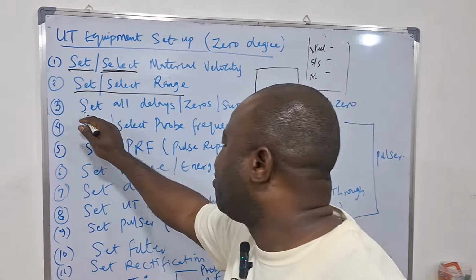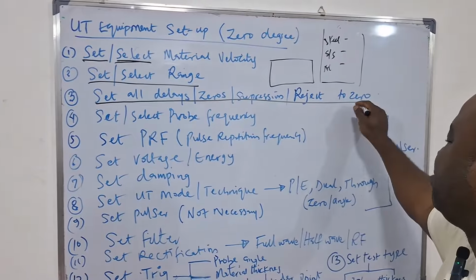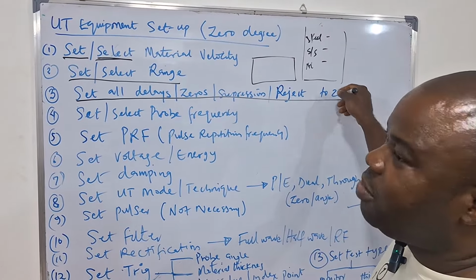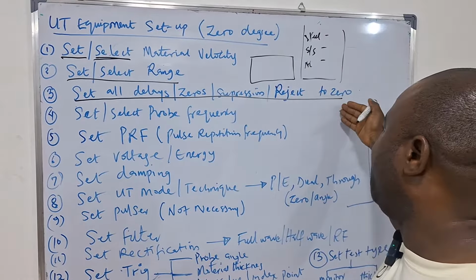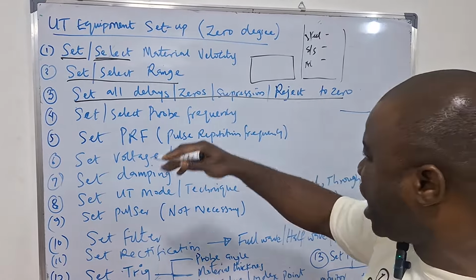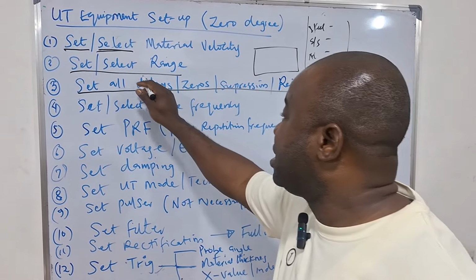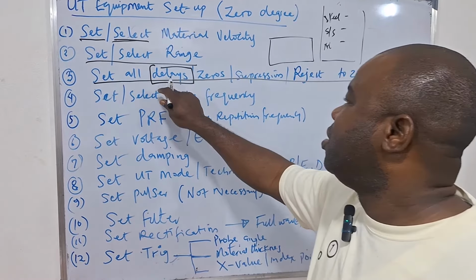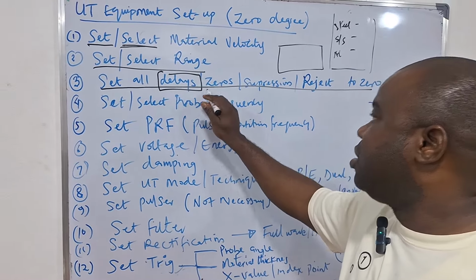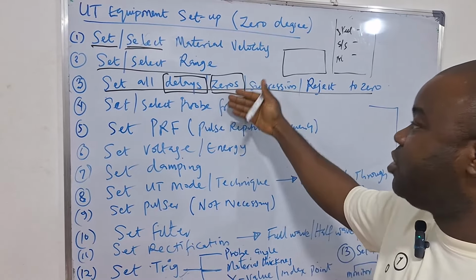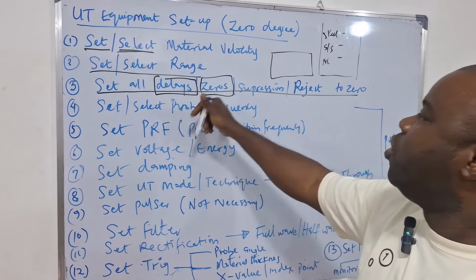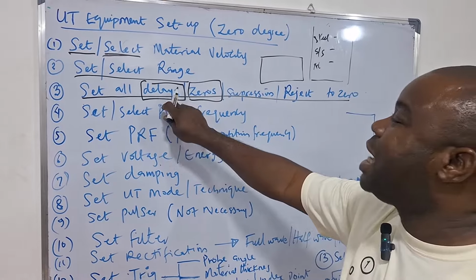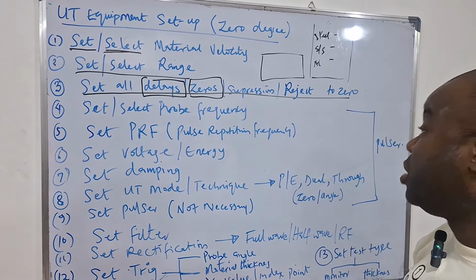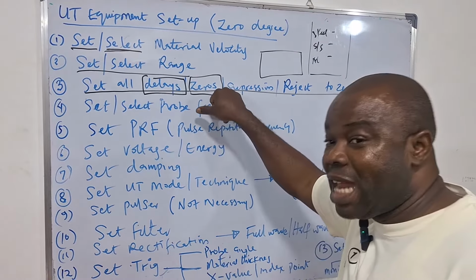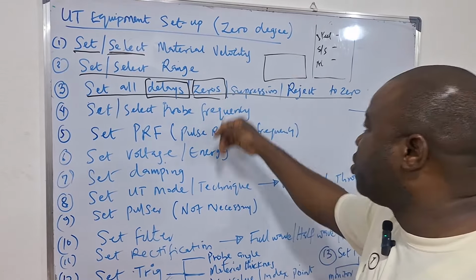This is very important before you proceed, because it might eventually affect some of the values you get. So just go around the unit. Some machines have delay only, some have zero only, some have both zero and delay. You need to set whatever value you see in the delay to 0, and whatever value you see at the zero to 0.